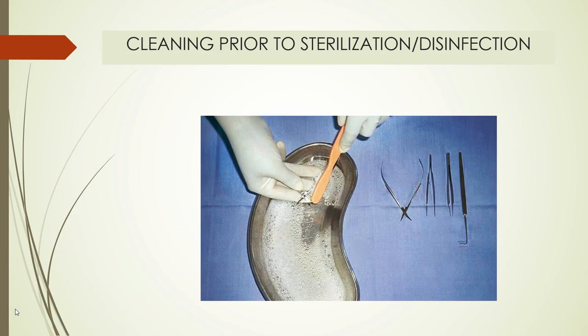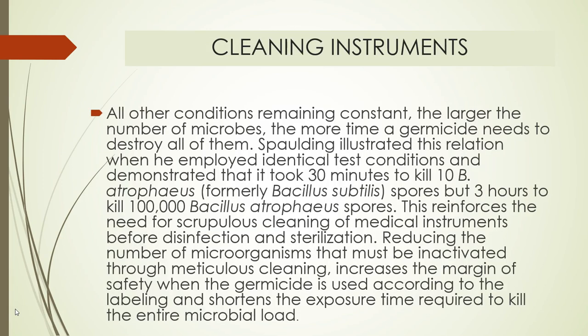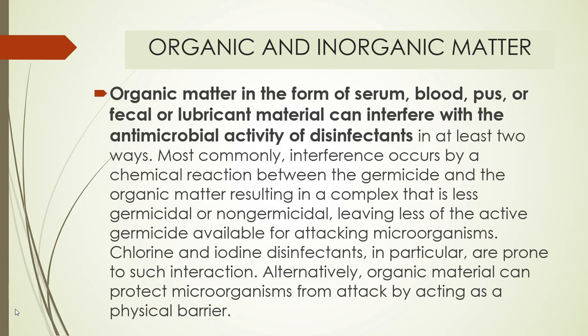Cleaning of the instrumentations, again, prior to disinfection is most important. So if you're using scissors and hemostats, things with hinges, they should be opened up and scrubbed before a disinfection. In general, the greater the degree of contamination or exposure to bacteria, the more time disinfectants require to destroy the organisms, so it is important to allow access of this. And so remember to instruct those responsible for cleaning that proper cleaning of the hinges is going to be important.